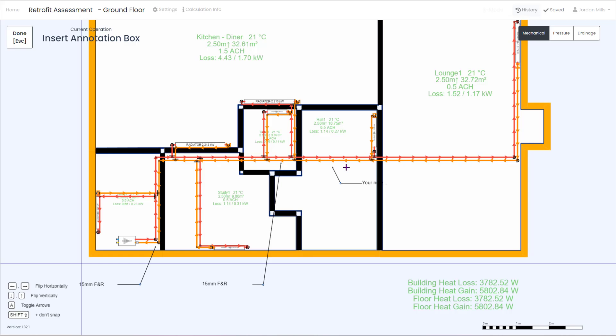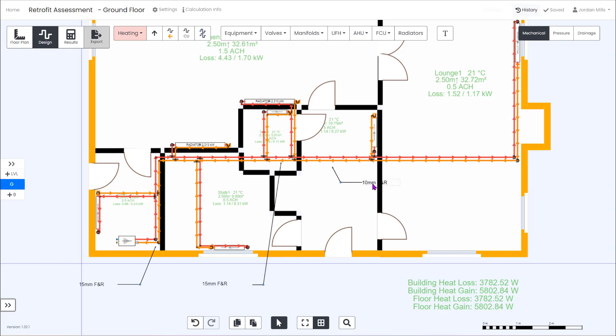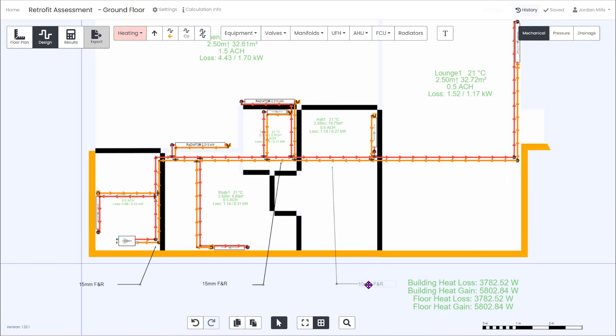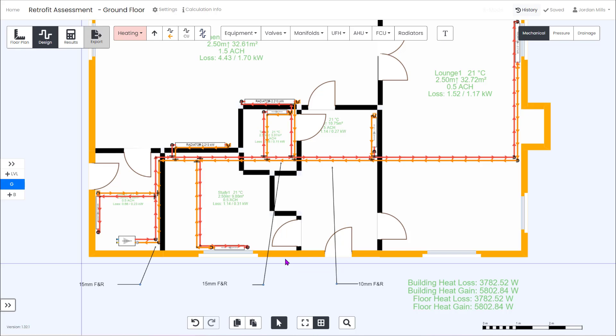From our site visit we know that all the radiators are piped on 10 mil. The main run to the hallway is 15 mil and the final run from the hallway and lounge is 10 mil. We're able to add notes to the drawing to identify this and compare to the calculated results later on.